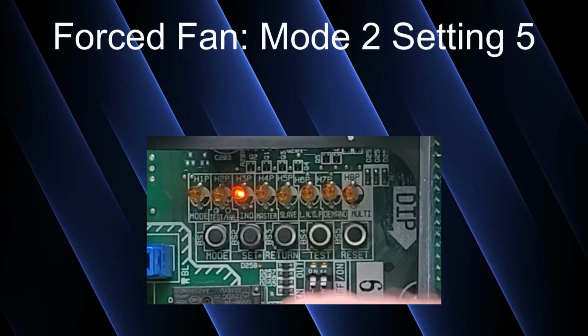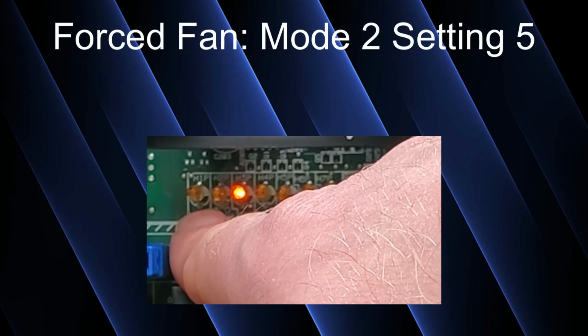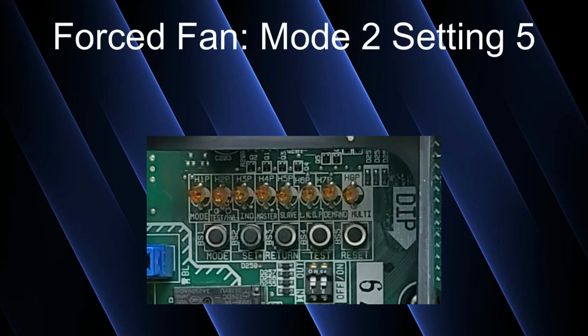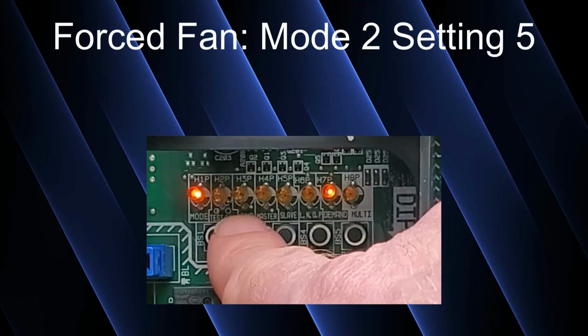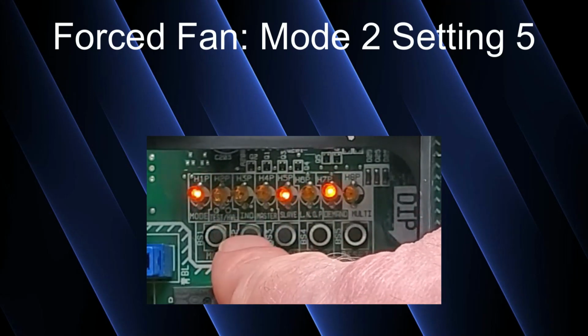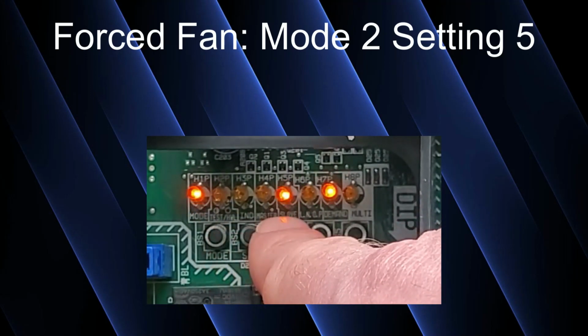So when you need to turn on or enable forced fan, again, you're going to start from the main screen. On the older boards, H3P is solid. This time we need to change a setting. So we're going to press and hold the mode button until H1P is solid. And then we're going to go to service mode 2, setting number 5. So H1P is solid. That tells us we're in service mode 2. Hit set 5 times. You know you've pressed it 5 times because H5P and H7P are on. That's 4 plus 1, which equals 5.